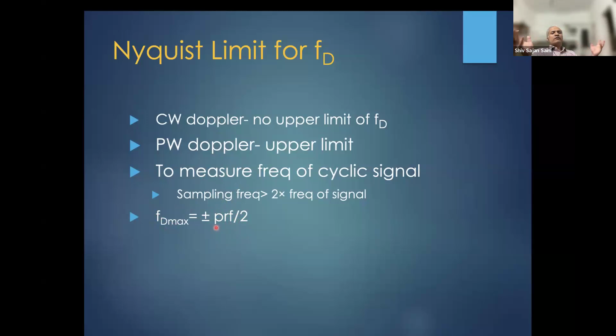So if we simplify this, the maximum Doppler shift should be plus minus half of the pulse repetition frequency. Pulse repetition frequency is the number of pulses which are sent in a unit time. So if my Doppler shift is more than half of the pulse repetition frequency, then I am going to have a loss of signals, which is known as aliasing. And let's see how.